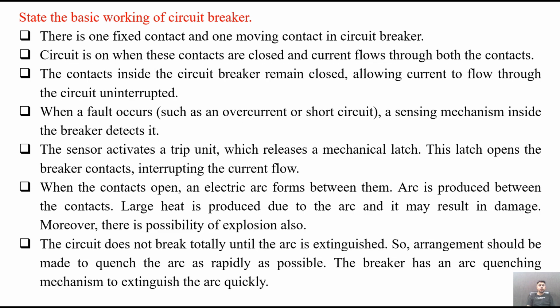State the basic working of circuit breaker. There is one fixed contact and one moving contact in a circuit breaker. The circuit is on when these contacts are closed like this and the current flows through both the contacts. The contacts inside the circuit breaker remain closed, allowing the current to flow through the circuit uninterrupted, meaning continuously from one end to the other end. Now when a fault occurs, such as an overcurrent or short circuit, a sensing mechanism inside the breaker detects the fault. The sensor activates the trip circuit or trip unit, which releases a mechanical latch. This latch opens the breaker contacts, interrupting the current flow.